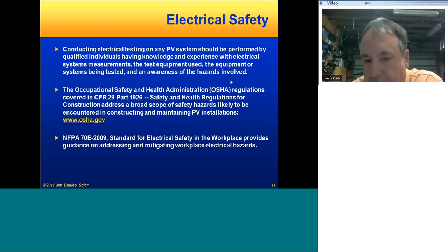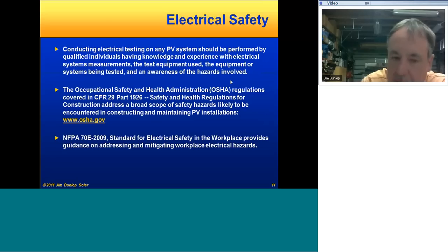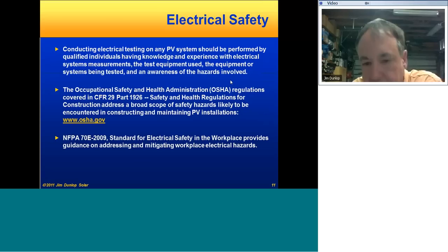But you have a couple standards here. Obviously, those standards have to do with a lot of the things in constructing and maintaining installations, the fall protection, the electrical hazards, and so forth. And then you've got the standard for electrical safety in the workplace from NFPA 70E that really covers a lot of details on how to recognize and address different workplace electrical hazards. And part of the things in there that are particularly important, I think, are determine the fault currents in these larger systems that, technically, you could have fault currents of the entire array fault back to one combiner box, and that's why the disconnects and things, and making sure we can work on those in a de-energized state.